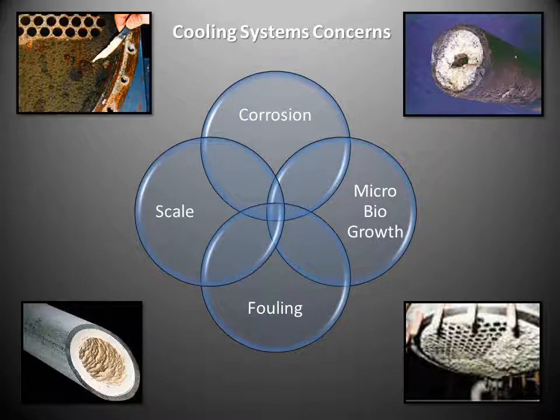The four main problems associated with cooling tower maintenance are corrosion, scale deposition, fouling, and microbiological growth. All of these must be addressed for a cooling system to remain clean, efficient, and problem-free.